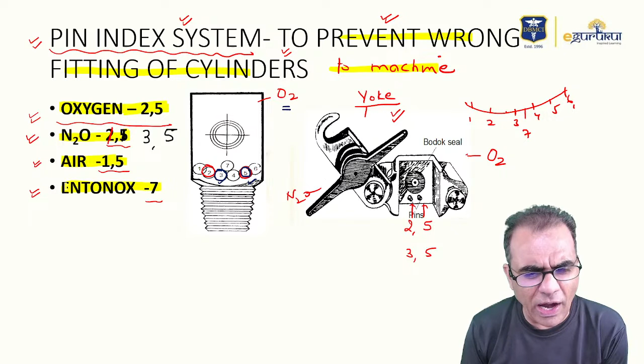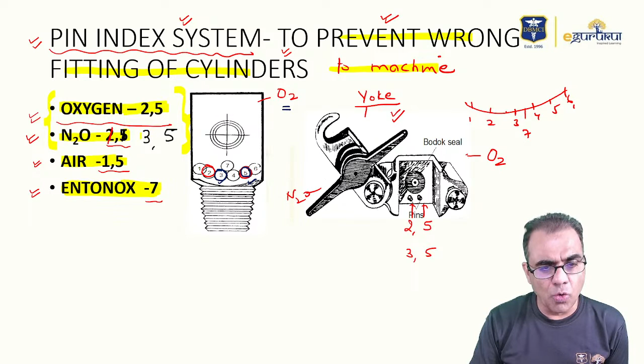Entonox 7, although Entonox through cylinders attaching to the anesthesia machine is also not supplied. So 90%, 95% or 99%, you are expected to know the pin index position of oxygen and nitrous oxide. Oxygen 2,5 and nitrous oxide 3,5.